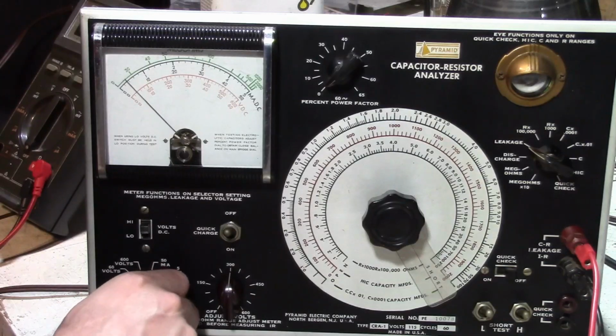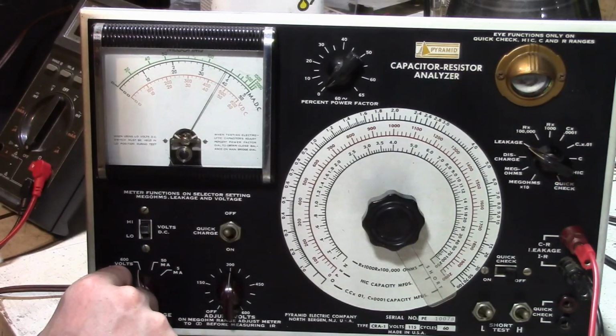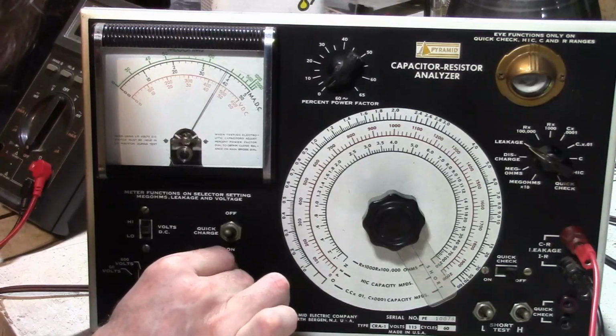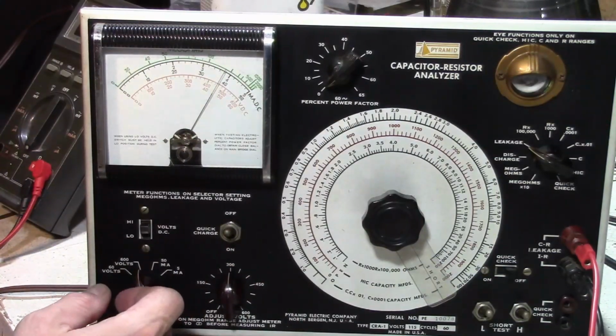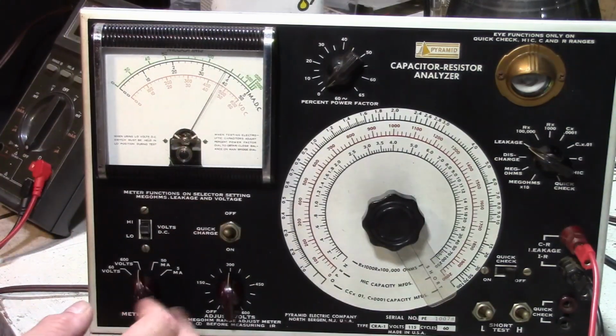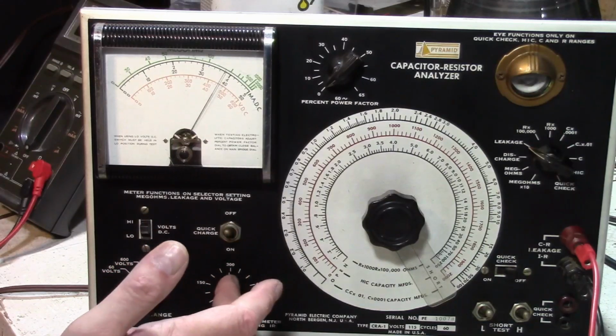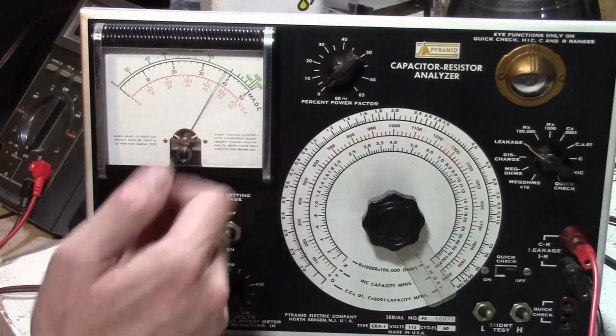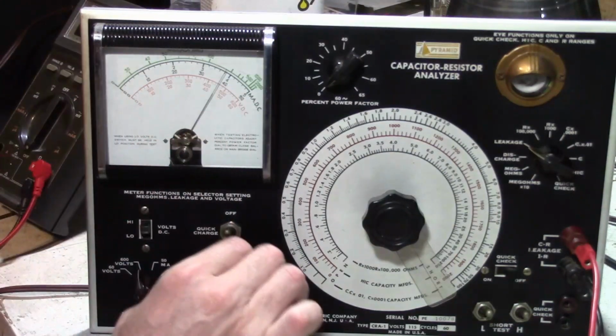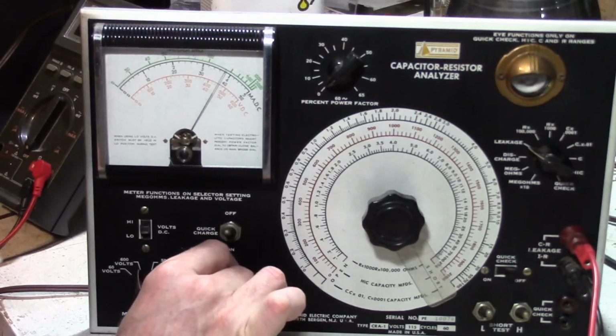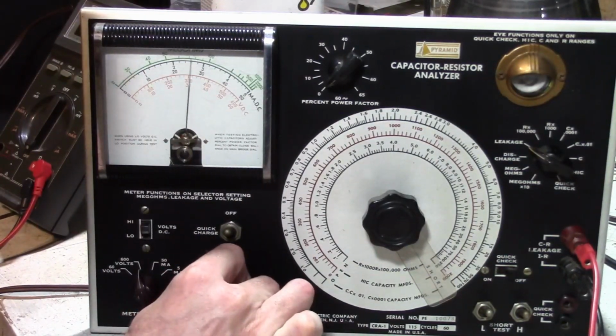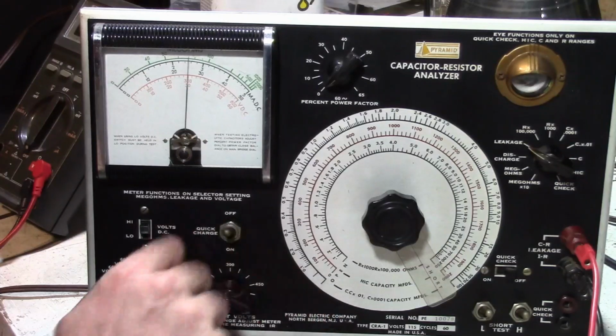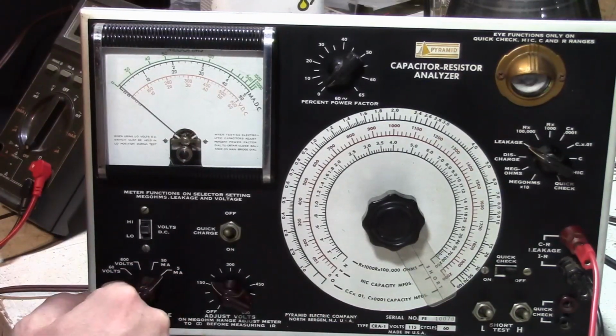It's supposed to be less than 10 milliamps, so let's see, 600 volt scale. I keep forgetting this knob. This is probably an issue now that I think about it, because we're only up halfway on this knob, but we're almost full scale on the voltmeter, so that's not so great. I didn't realize I was already up to 450 volts, so let's back this down to 300 volts. And now let's check the currents.